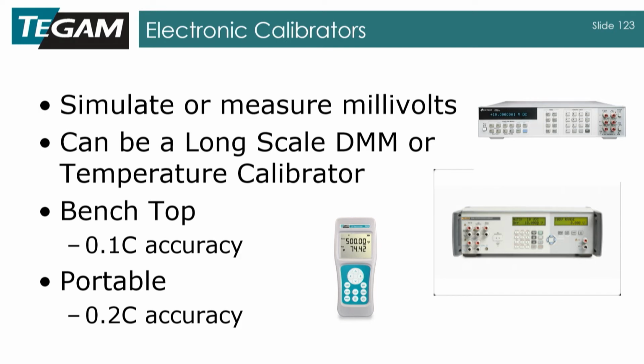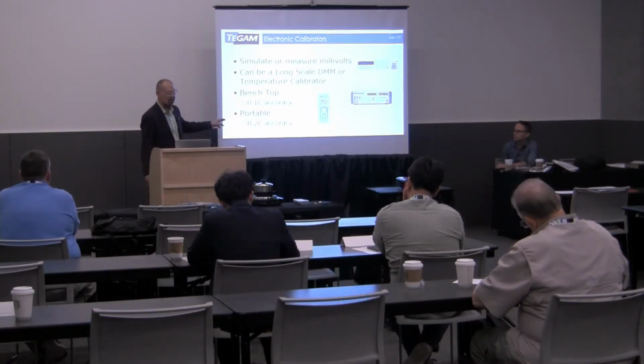If you're using a calibrator, you could use a benchtop or a portable. A benchtop calibrator like this, Fluke 7526, is actually an old Martel product that Fluke still makes, but that's kind of a dedicated temperature calibrator. It's pretty nice. It's meant for use in a lab. You get about 1/10 of a degree accuracy. And a portable, this is our new one that I know a lot about, so I'm going to use that and reference that later.